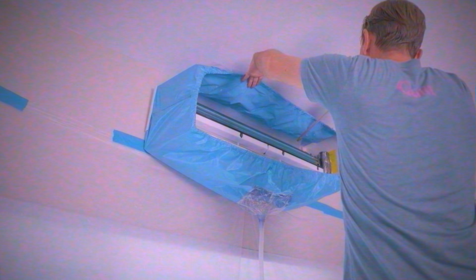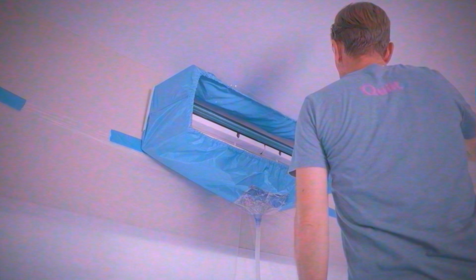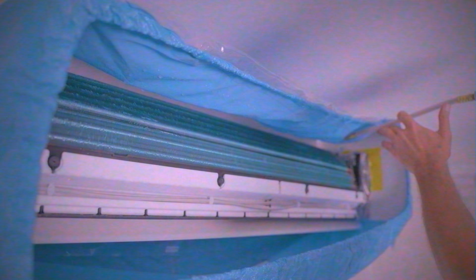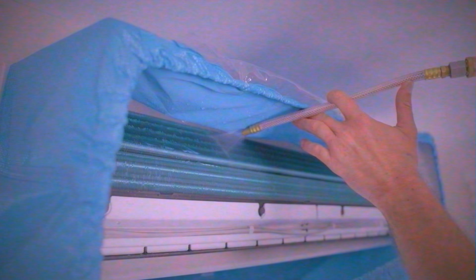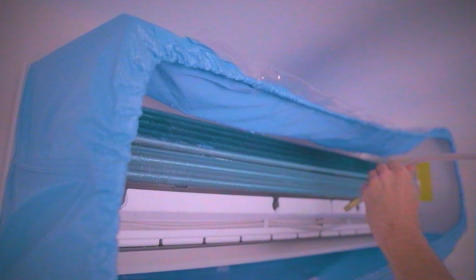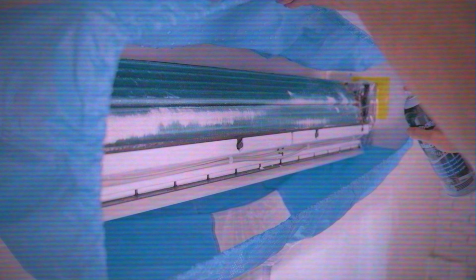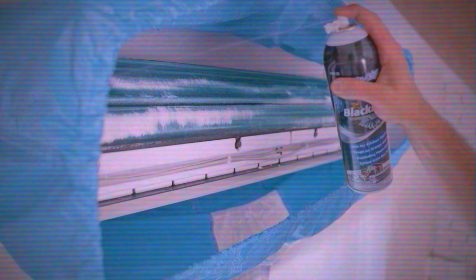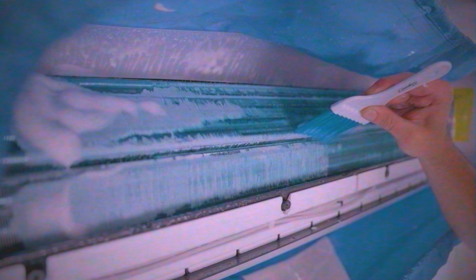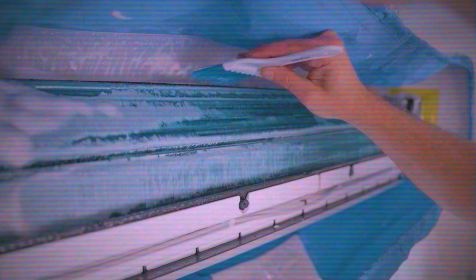Using the low-pressure sprayer, spray water or cleaning solution evenly across the surface of the heat exchanger. Next, spray canned coil cleaner evenly across the heat exchanger and allow it to sit for at least 2 minutes. For stubborn buildup, use a soft brush to gently loosen debris.